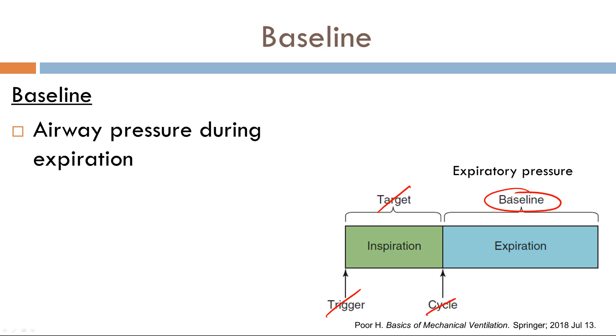The definition is quite straightforward. It is the airway pressure during expiration. Now up to this point, the first three variables we talked about — trigger, target, and cycle — were during inspiration. The baseline phase is the only variable that's during expiration.